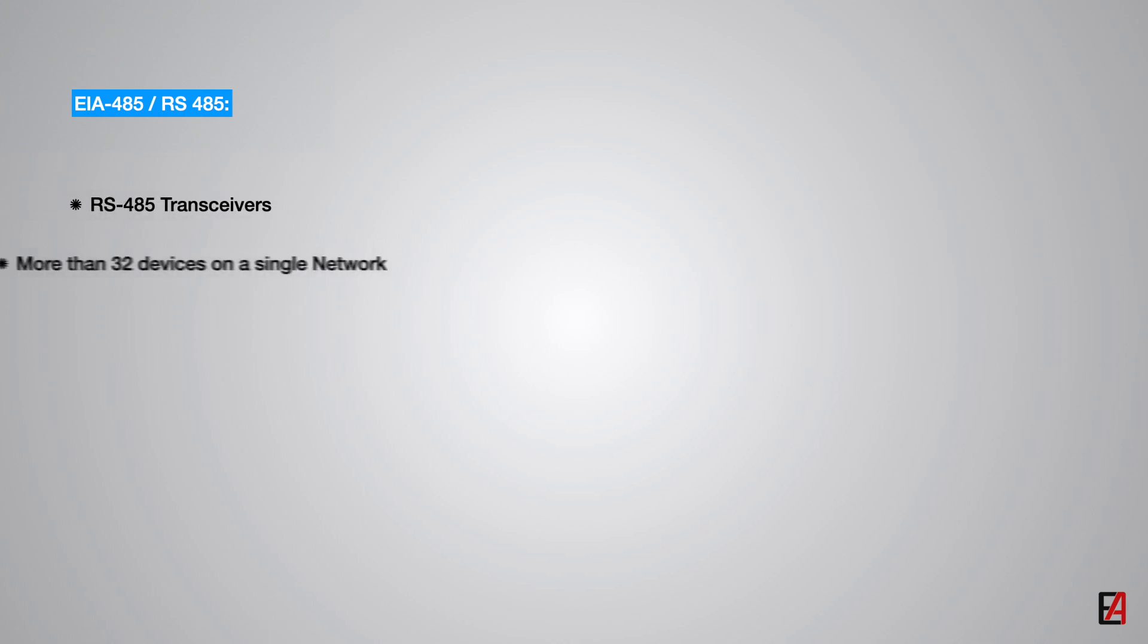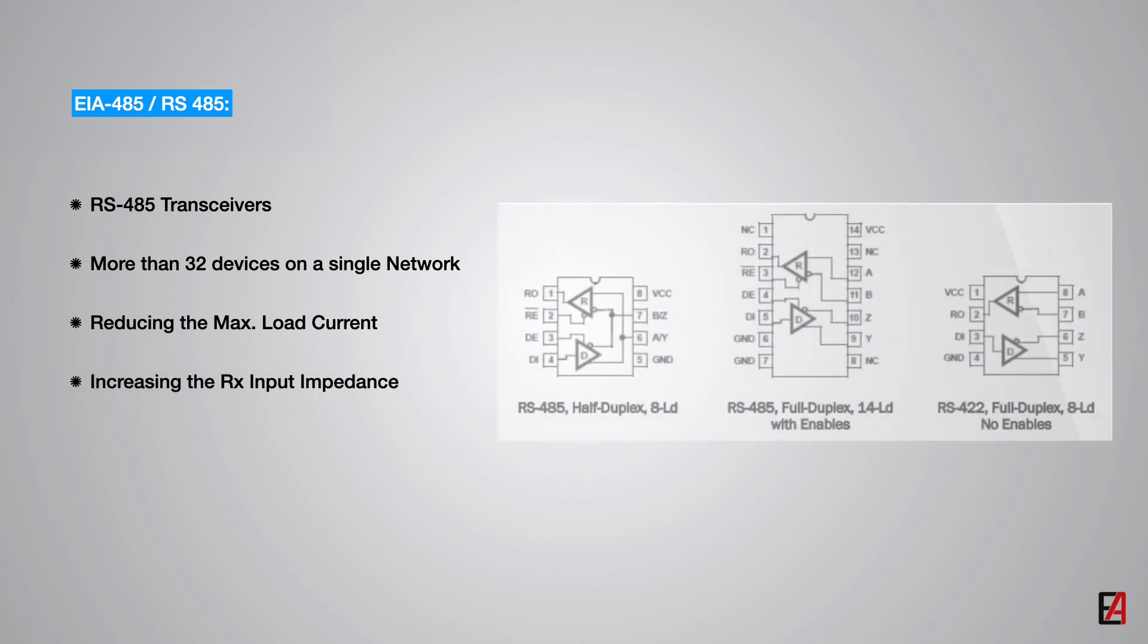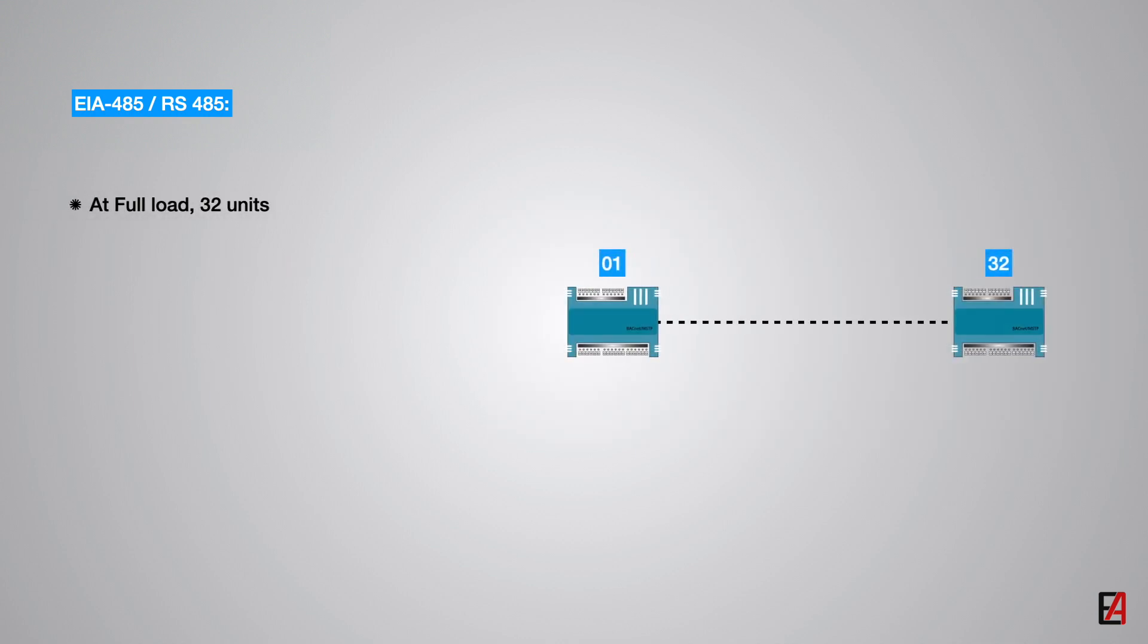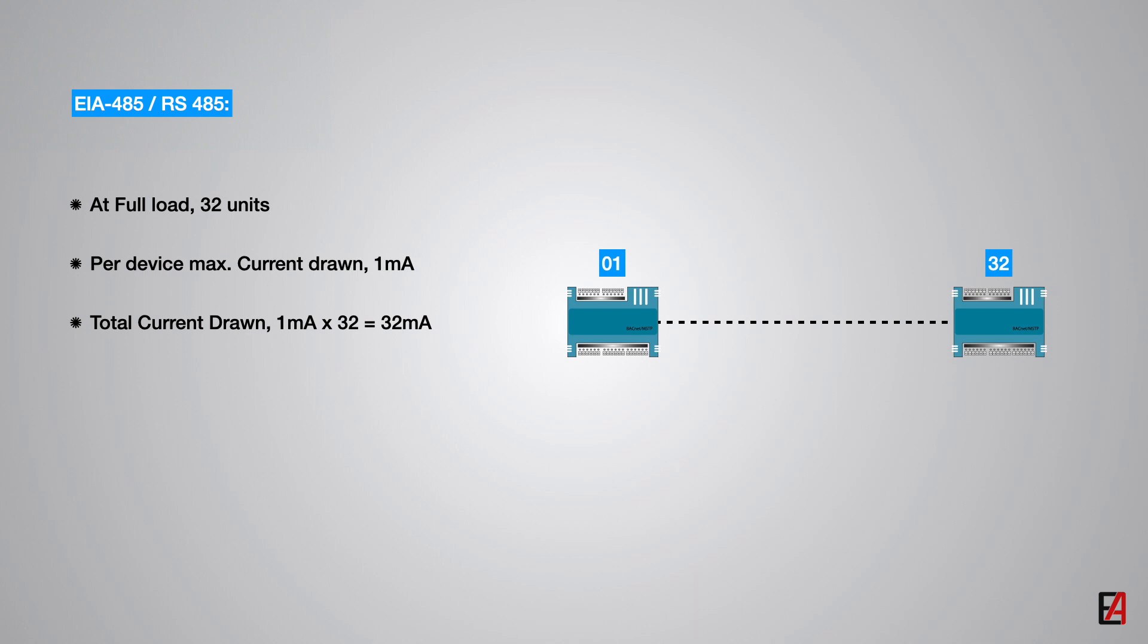Thanks to advancement in RS-485 transceivers, we can now connect more than 32 devices on a single MSTP network without the need of repeaters. This is achieved by reducing the maximum load current of each transceiver by implementing a higher receiver input impedance. At full load, only 32 devices can be connected in a single network without repeaters. Each device's maximum drawing current is 1 mA with the total current drawn is 32 mA which complies to the RS-485 standards requirement.